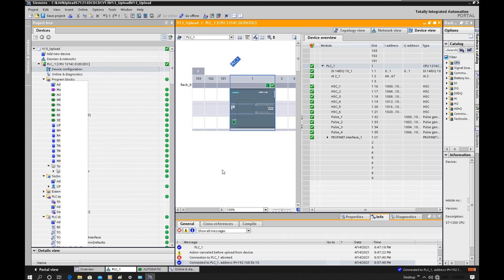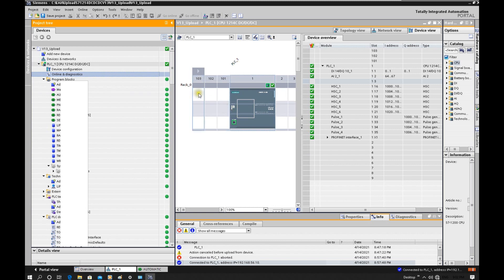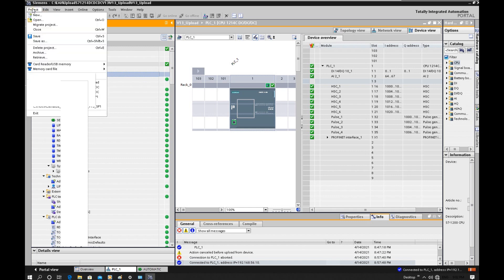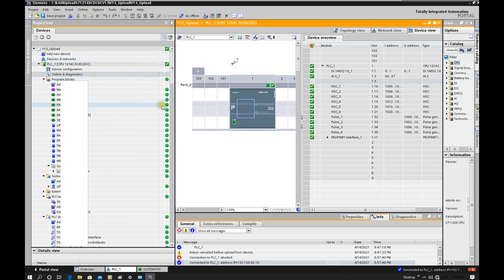Upgrading the firmware will not wipe out the existing program or IP address. The upgrade only takes a couple of minutes, and some good features and bugs will be solved. But even though this is a good feature, I still highly recommend that before you do the CPU firmware upgrade, you upload the program first — make sure your program is archived and saved correctly. Then upgrade the CPU firmware. After the program upload, archive your project by saving first and then using the archive function to zip the project into a small file.